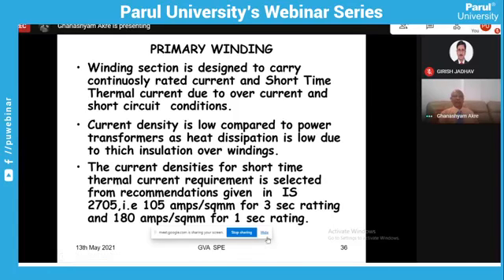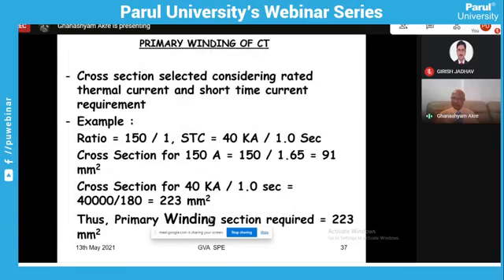An example I can just give you. The current transformer is rated for 100 by 1 ampere, and its short circuit current rating is 40 kiloamperes for 3 seconds. That is what the utilities are requiring today. So the same transformer, even at 100 amperes, which is low current, we need to provide the cross-sectional area of the primary in such a way that it will withstand 40 kiloamperes for 3 seconds also. And in IEC and IS, these current densities are also specified for taking care of the short circuit current. That means if it is a 3-second rating, its current density should be 105 amperes per square millimeter or less, and for a 1-second rating, it can be 180. Just one example, to give you the idea of the difference.